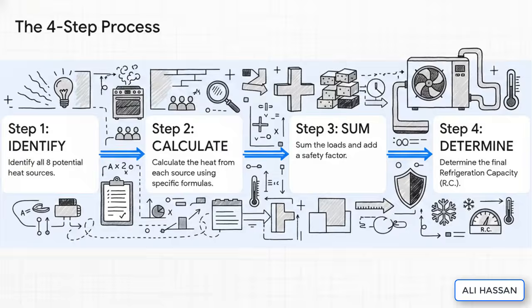It's a lot, but it all comes together in this pretty clear four-step process. First, you identify every single potential heat source that we just listed. Second, you use a bunch of specific formulas to calculate the load from each one. Third, you add them all up. And finally, you determine the total refrigeration capacity you need to handle that total heat load.